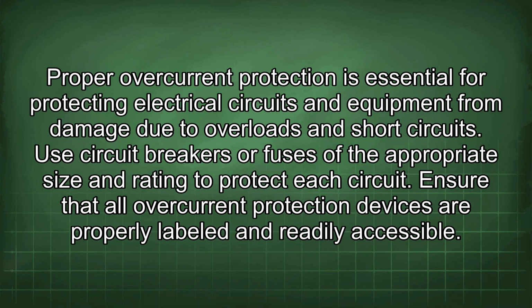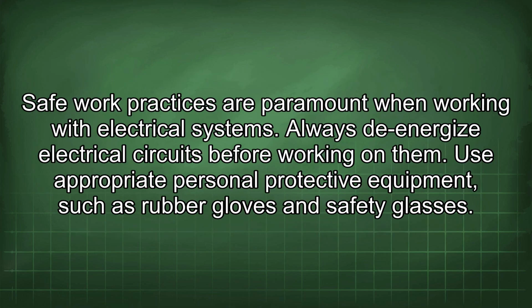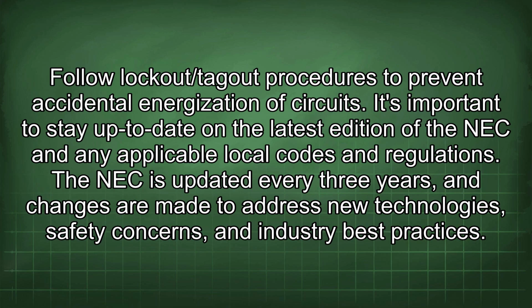Proper overcurrent protection is essential for protecting electrical circuits and equipment from damage due to overloads and short circuits. Use circuit breakers or fuses of the appropriate size and rating to protect each circuit. Ensure that all overcurrent protection devices are properly labeled and readily accessible. Safe work practices are paramount when working with electrical systems. Always de-energize electrical circuits before working on them. Use appropriate personal protective equipment, such as rubber gloves and safety glasses. Follow lockout/tagout procedures to prevent accidental energization of circuits.